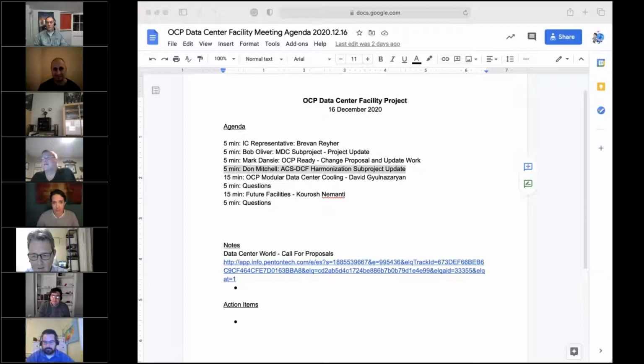So the point is, would we do anything different than the ASHRAE standard? That's a great question, but especially as we start looking at adding liquid cooling to the IT racks in a slab floor environment, which is where most data centers are going, your piping is going to go overhead. And a lot of the technologies we're sponsoring with ACS operate at elevated temperature liquids. So the question would be door heat exchangers.